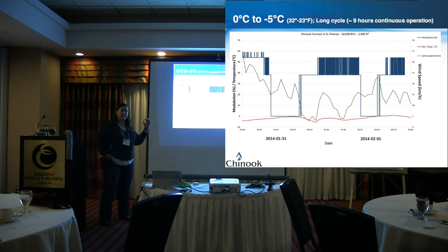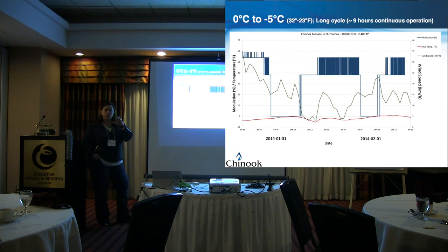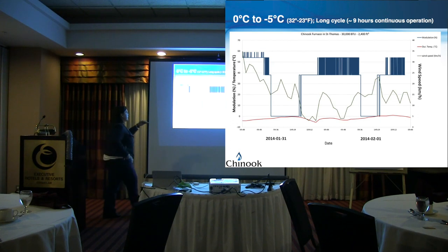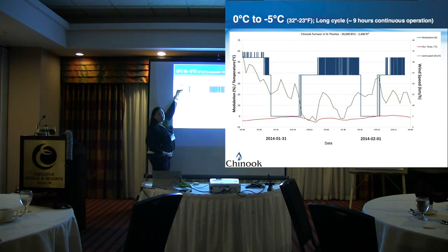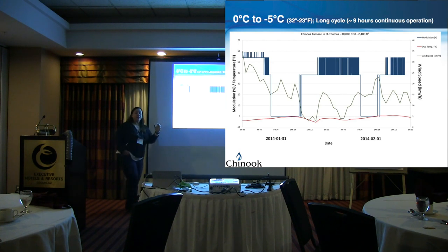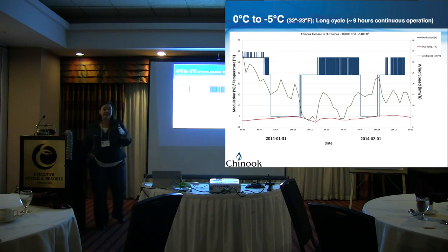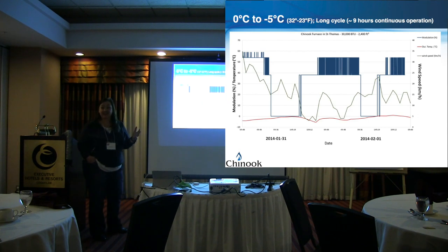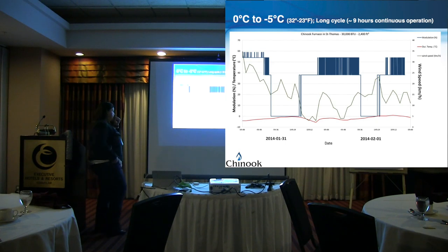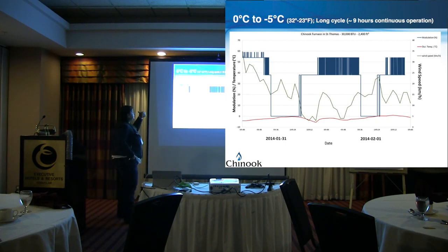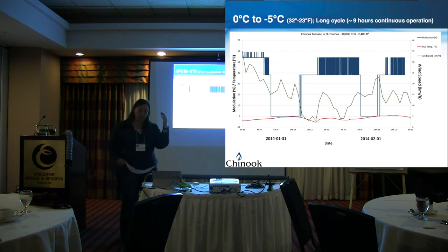So what you'll see here is, with the right size system, so the load at 28,000, just over, we put in the 30. And so you'll see the equipment is modulating between 40 and 60% of its capacity. It doesn't go over 60%. So that also shows, even in F280, we still have a lot of fudge factor in there if the equipment's only running at 40 to 60% of its capacity on average. So the sun comes up during the day, house is at temperature, it's a high performance house, system turns off. And then when it's needed, it ramps back up again and runs 40 to 60% of its capacity.